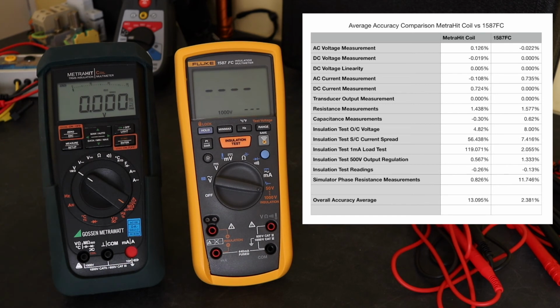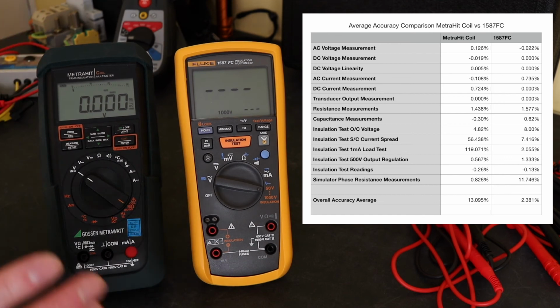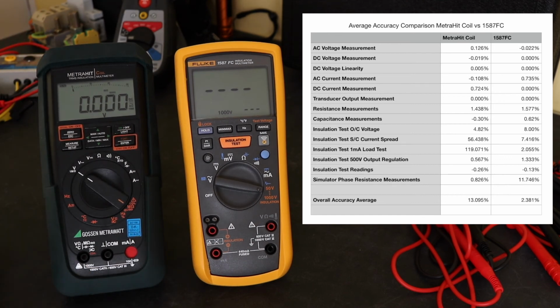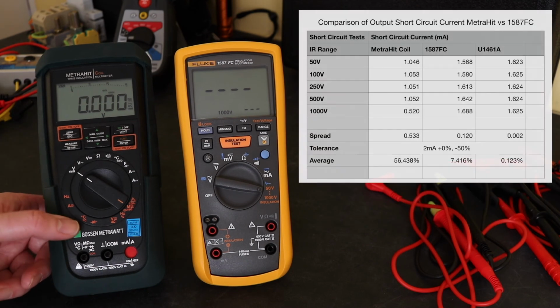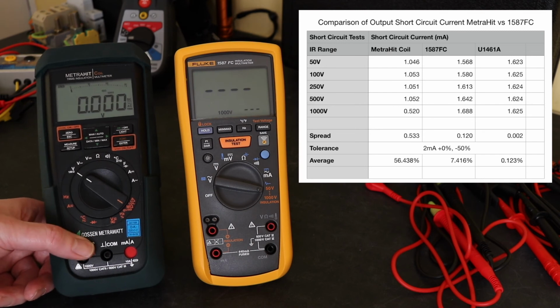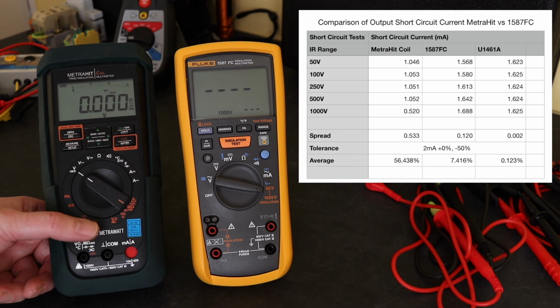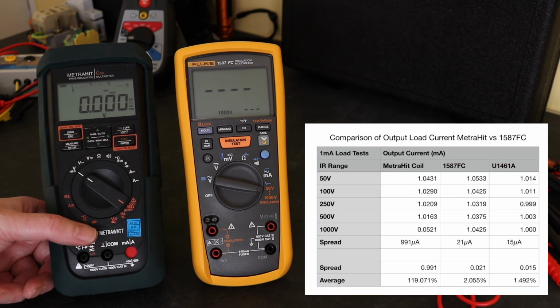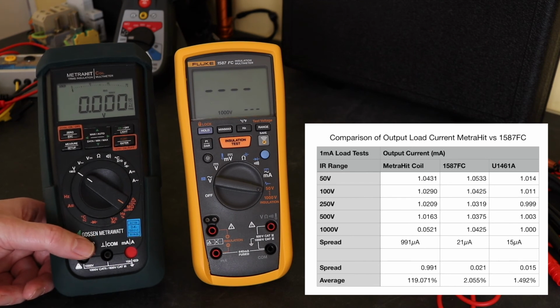Resistance, again, not much to choose between them really, as is capacitance, not an awful lot there. And then we move on to some quite interesting results with the insulation testing function. Open circuit volts test, better for the MetraHit coil, but the IEC standard is a 20% tolerance, so nothing to worry about there with those results. Short circuit spread and 1 milliamp load current. There is a massive problem with this MetraHit coil, which again, Gossen Metrawatt don't want to talk to me about. But you see, I'll put the actual results up for the tests, and you see on the 1000 volt scale, this cannot produce a 1 milliamp load. As a consequence, you get a huge spread on the short circuit currents, and you don't get the 1 milliamp test functioning, which is quite surprising because that is a requirement of the IEC standard.